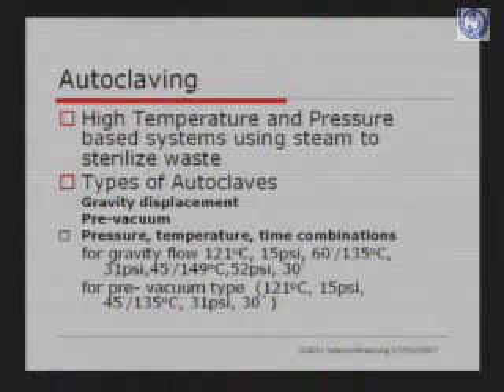It's only in the 1970s that we started autoclaving for waste treatment, but now it's getting very popular because of easy handling and usage. There are two types of autoclaves that have been used: the gravity displacement and the pre-vacuum autoclaves. As you can see, autoclaving is a high temperature and pressure based system using steam to sterilize waste. Here in gravity displacement, we just use the steam pressure to displace the air, and in the pre-vacuum system, a vacuum is used to evacuate the air, and then the steam is introduced into the autoclave. Then different pressure, temperature and time combinations are prescribed for effective autoclaving and disinfection of waste.